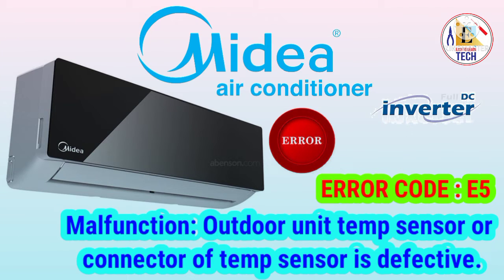When you see in your unit the error E5, it means outdoor unit temperature sensor problem or the connector of the temperature sensor is defective. First of all, you have to check the placement of your sensor and the connector, if the connector is connected properly in the PCB or not. If it is connected properly, then you have to check the placement of your temperature sensor.